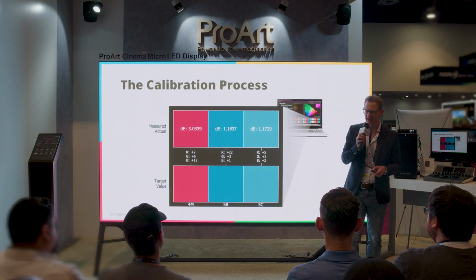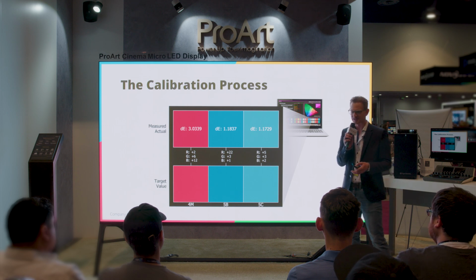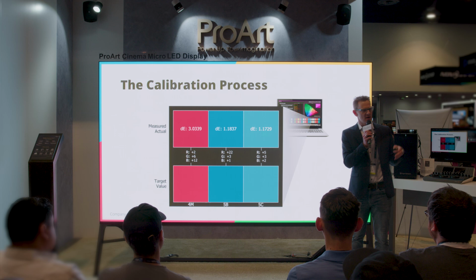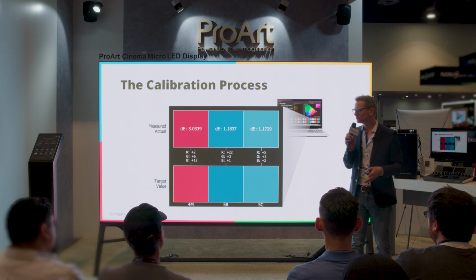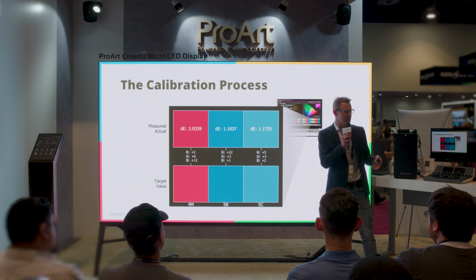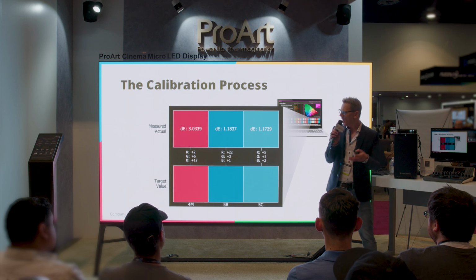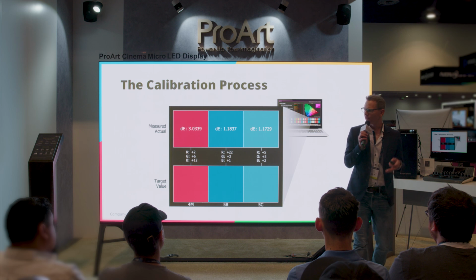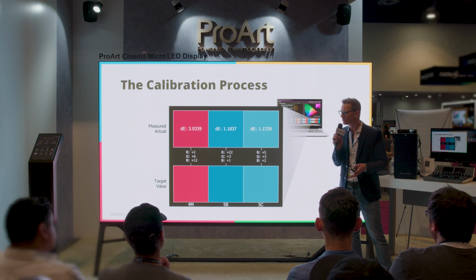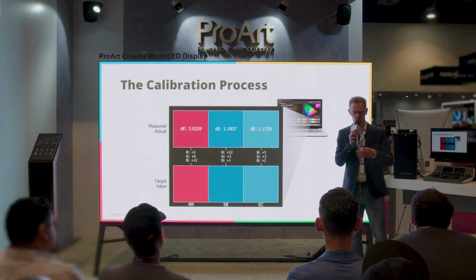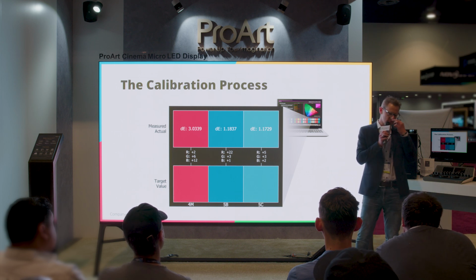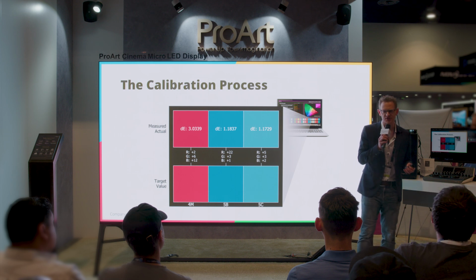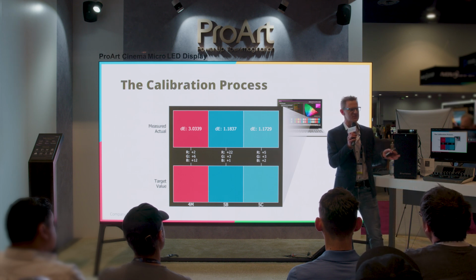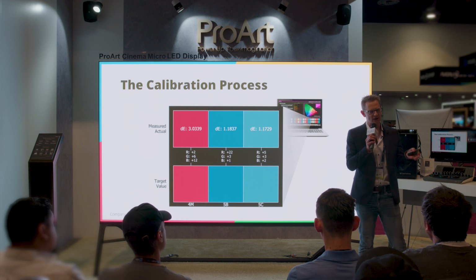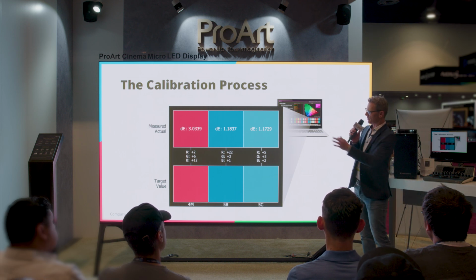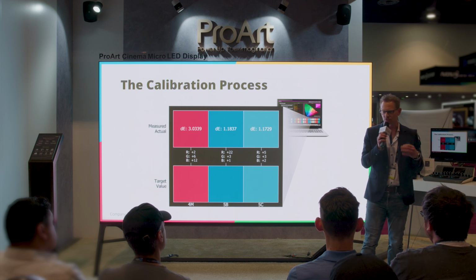So what we do in the calibration process, we take a reading of a specific test pattern, and then we're comparing that reading with the target. So every reference pattern basically is our target, and we compare this and see how far away we actually are from what the display actually should display. And that's what we call the delta or the offset. And human vision is nonlinear. There are specific colors we're much easier going with our eyes, and others we're very critical, depending on what you actually see. And so a color calibration software is designed to take that into account.